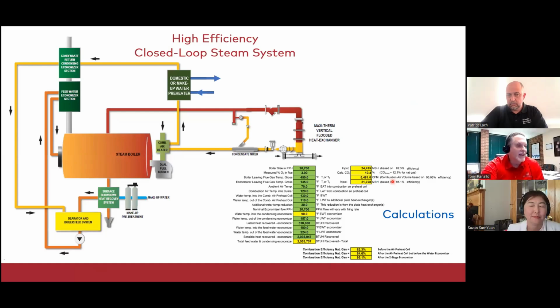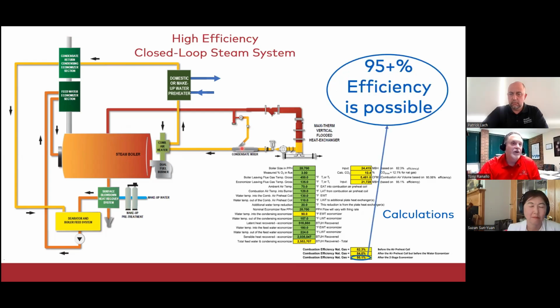What we're doing here, and the key to this, is our low temperature condensate that we can get from a Maxi-Therm vertical flooded heat exchanger. Once we have that cool condensate, we can start doing things with that. We can preheat some combustion air, which is one of the tips that we just saw on the previous page. We can use that to preheat some makeup water or some other process, maybe snow melt, things like that. Once we have very low condensate temperature, we can take that now into the condensing section of a two-stage economizer and bring this boiler efficiency up to about 95%.